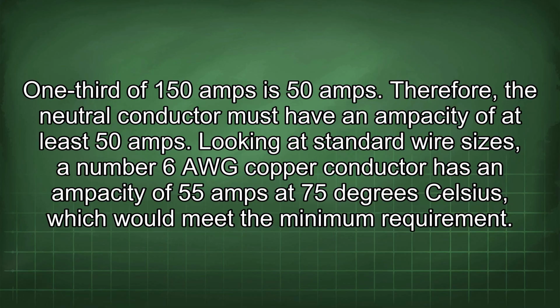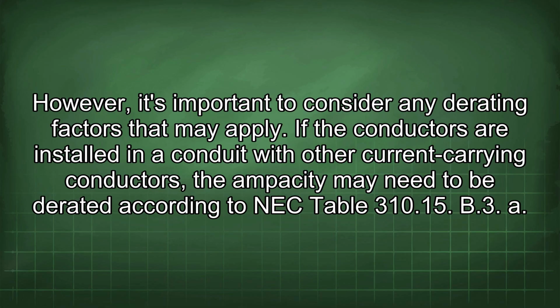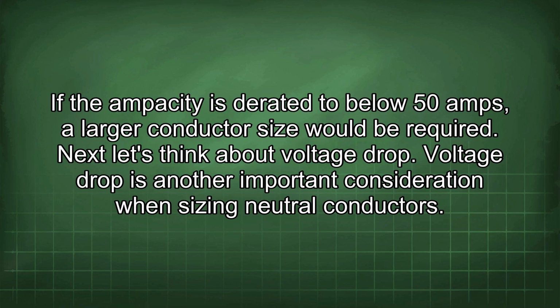Looking at standard wire sizes, a number 6 AWG copper conductor has an ampacity of 55 amps at 75 degrees Celsius, which would meet the minimum requirement. However, it's important to consider any derating factors that may apply. If the conductors are installed in a conduit with other current-carrying conductors, the ampacity may need to be derated according to NEC Table 310.15(B). If the ampacity is derated to below 50 amps, a larger conductor size would be required.